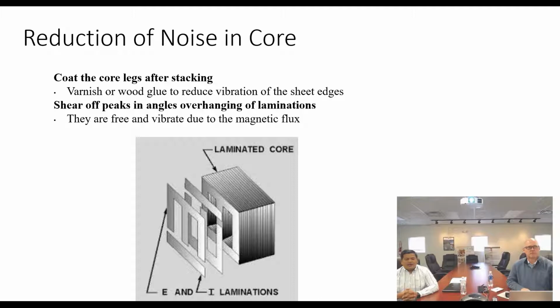Bottom yoke of the core and core legs are stacked, and after stacking, we apply a varnish or wood glue around them. That will help to fill the air gap, and also help us to keep the core laminations in one place, tightened together, or glued on the edges, so that the edges don't vibrate. Also, when we have the core construction, we have horns at the end of the core, and these horns or peaks are really in the air, or in the oil, and they're free to vibrate because they are not being clamped.